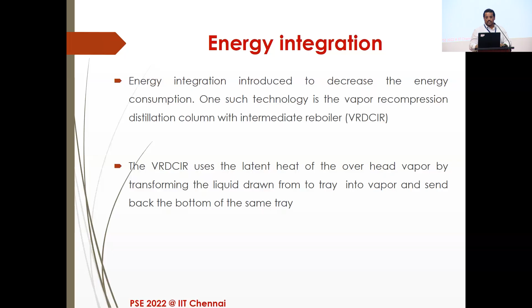recompression. So in this process, some part of the overhead vapor will be compressed, and because of that compression, the boiling point elevation will occur. That will be used to heat the reboiler stream. By this way it can reduce the load on the reboiler as well as the condenser. Why? Because the amount of vapor that we are not sending to the condenser does not need to be condensed.